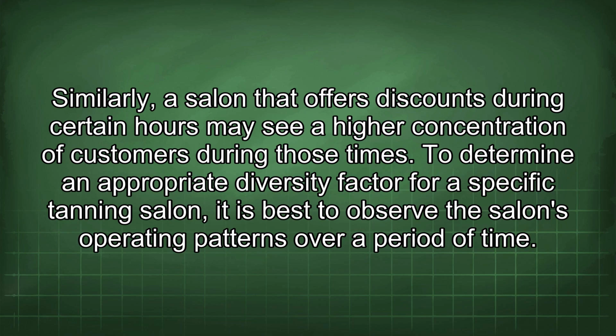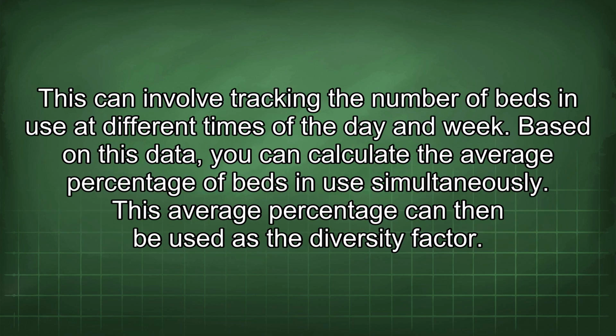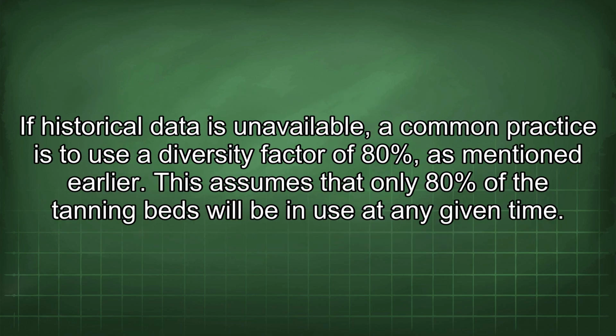Similarly, a salon that offers discounts during certain hours may see a high concentration of customers during those times. To determine an appropriate diversity factor for a specific tanning salon, it is best to observe the salon's operating patterns over a period of time. This can involve tracking the number of beds in use at different times of the day and week. Based on this data, you can calculate the average percentage of beds in use simultaneously. This average percentage can then be used as the diversity factor. If historical data is unavailable, a common practice is to use a diversity factor of 80%, as mentioned earlier. This assumes that only 80% of the tanning beds will be in use at any given time.